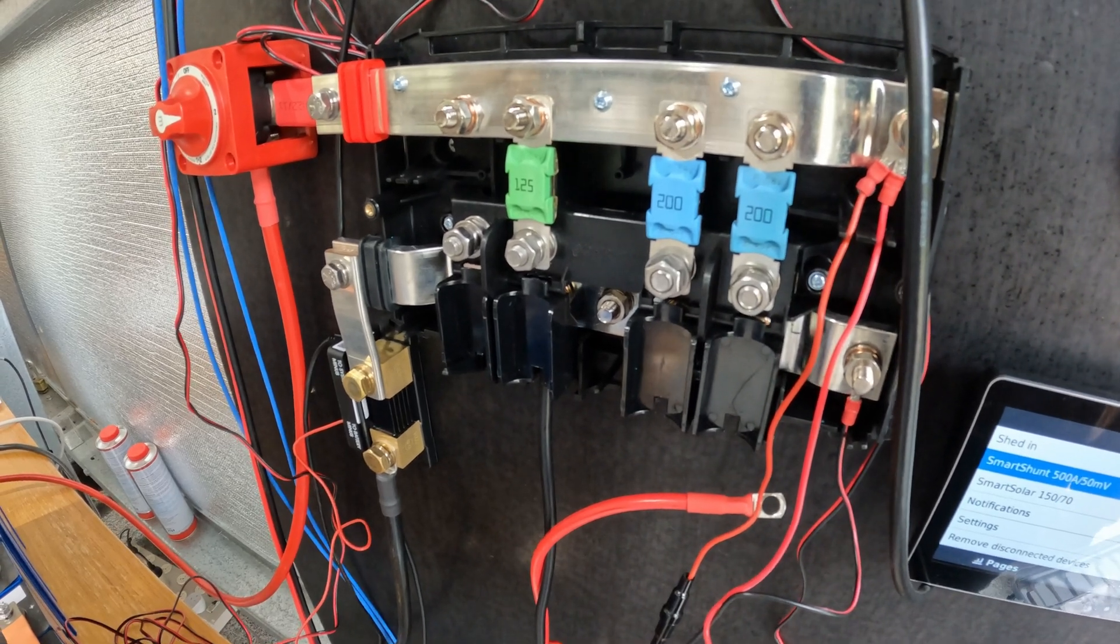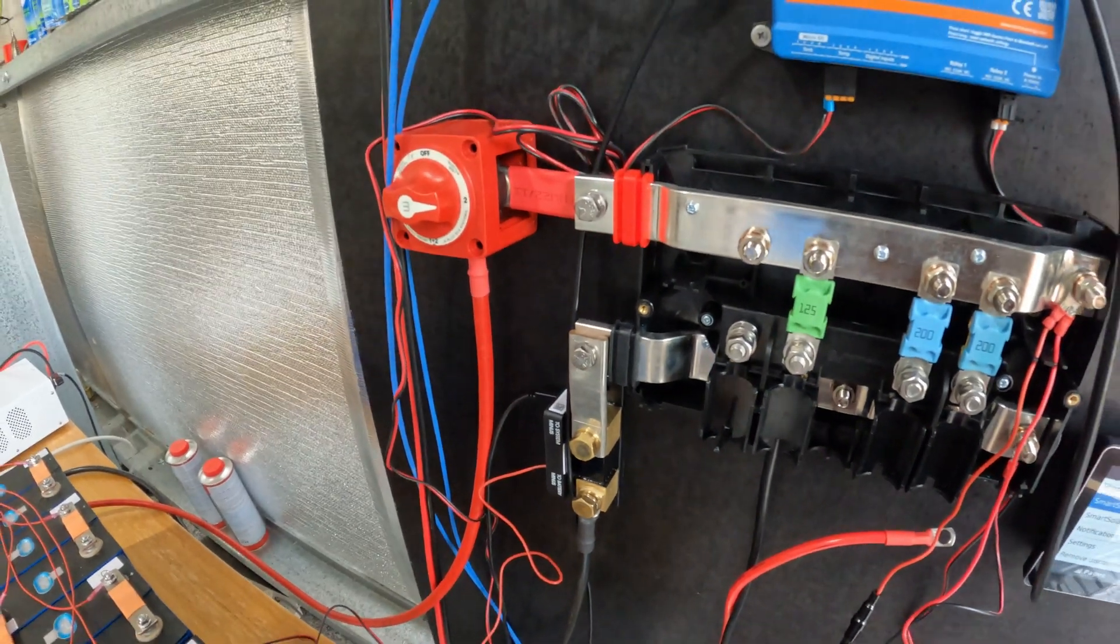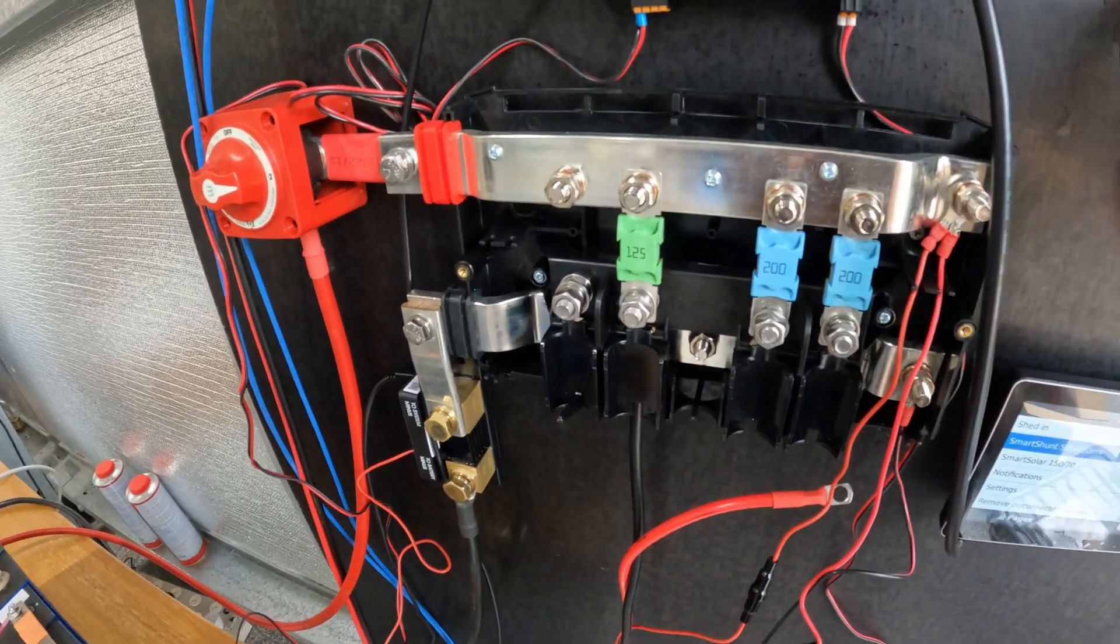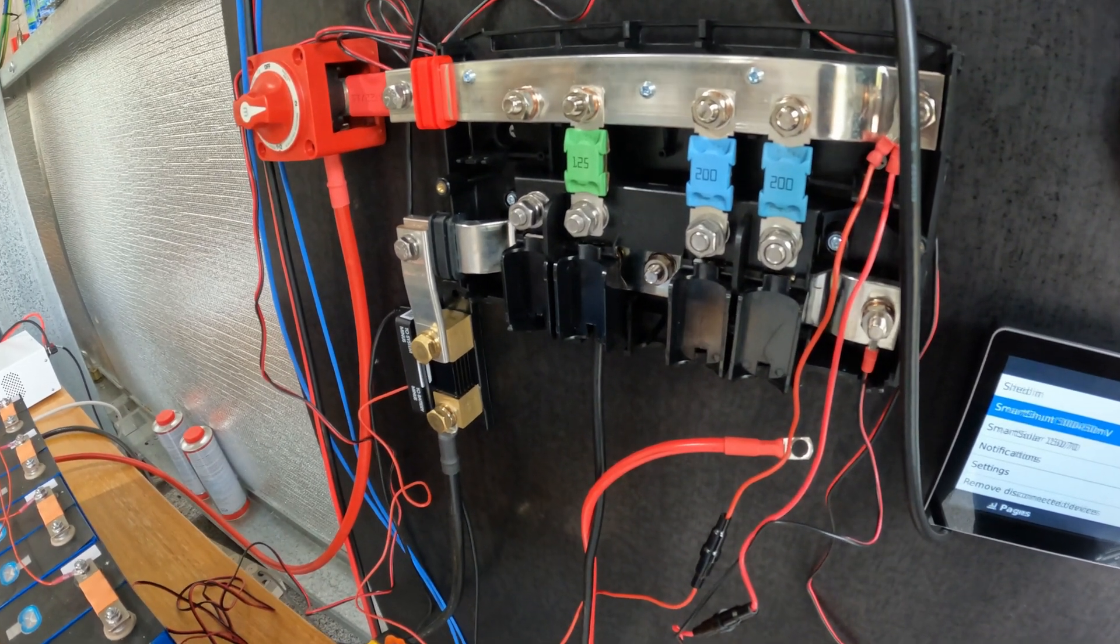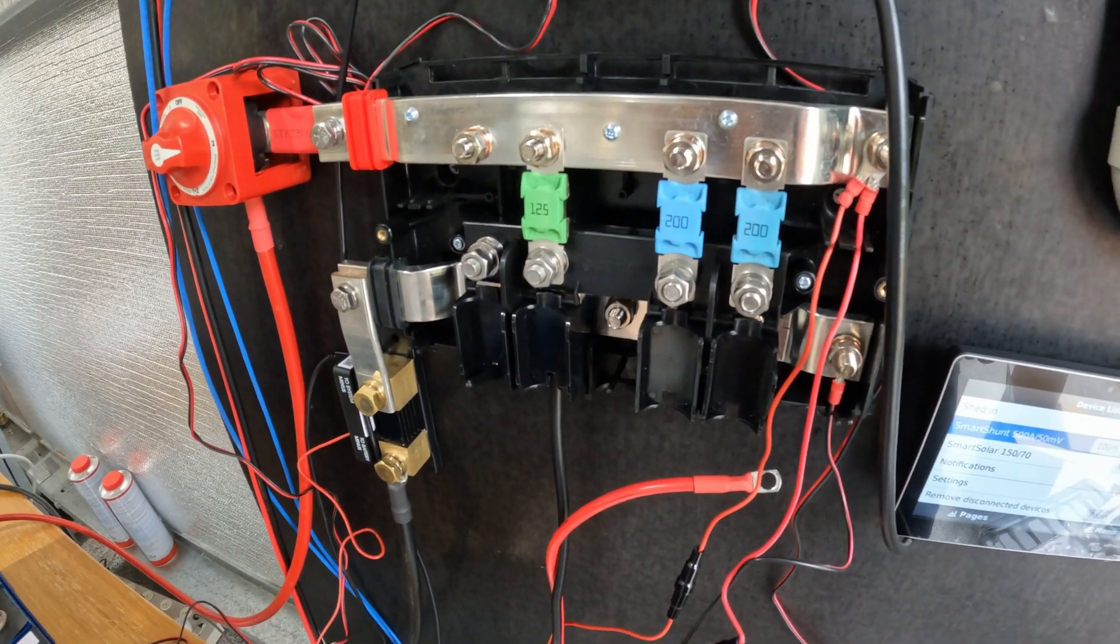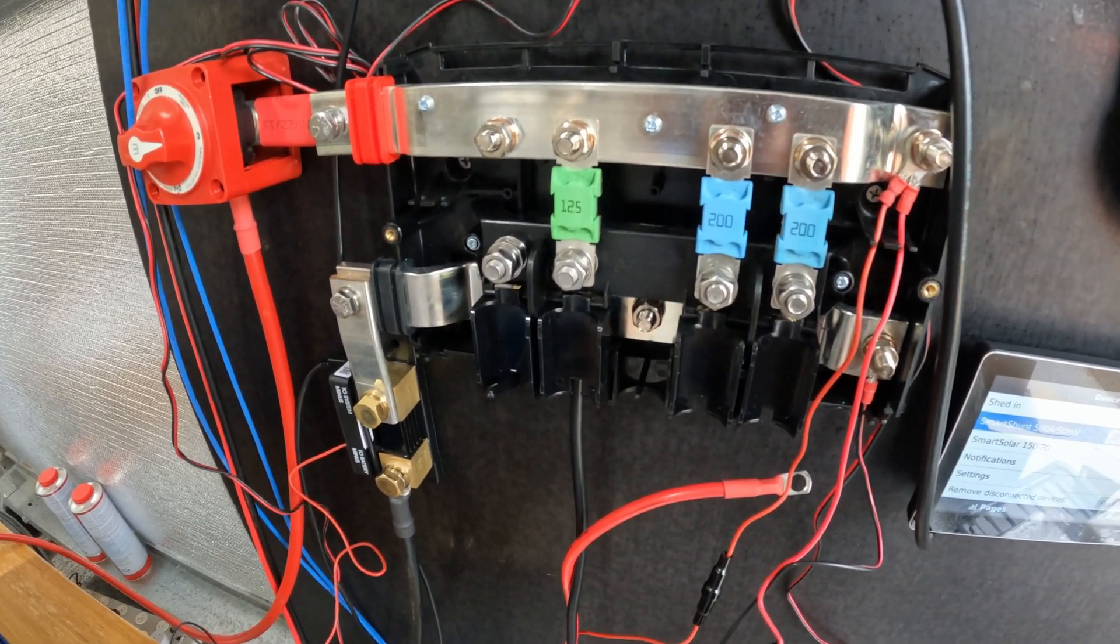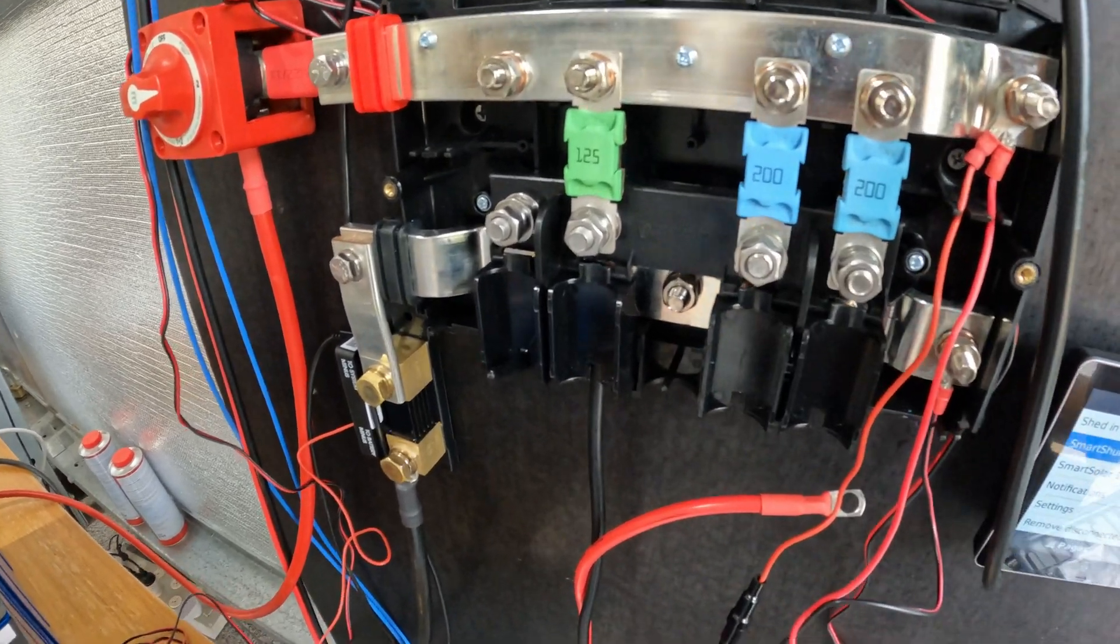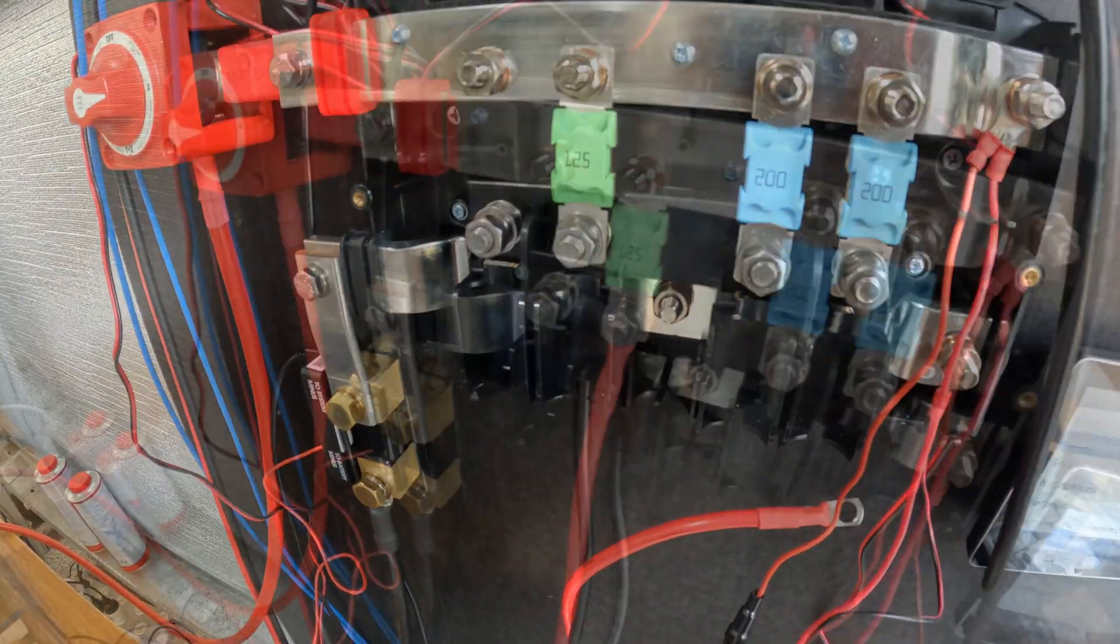So it's a live system. With the battery the way it is, it can pump out a lot of amps in a very short time. The capacitors that they use in things like the chargers and the inverters effectively act like a dead short, so it can either upset your BMS, upset the equipment, or you can blow fuses because the current that comes out of batteries can easily overwhelm. So I'm gonna give this a red hot crack using the pre-charge.